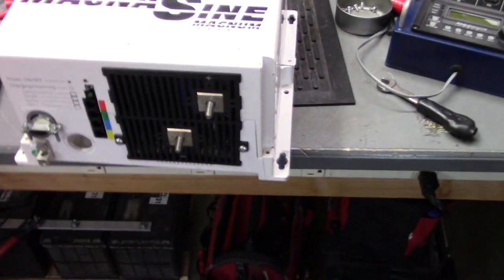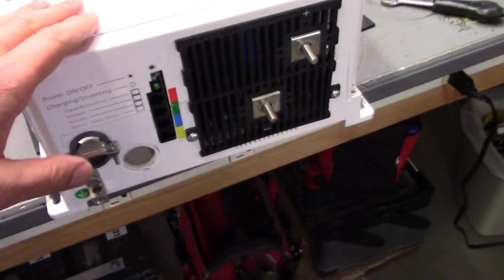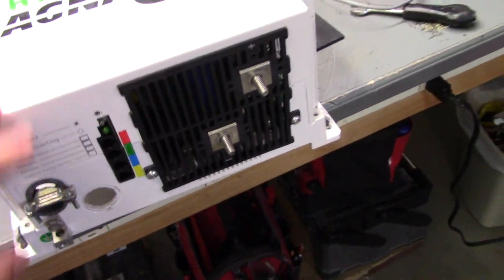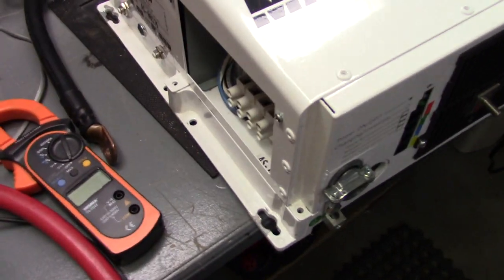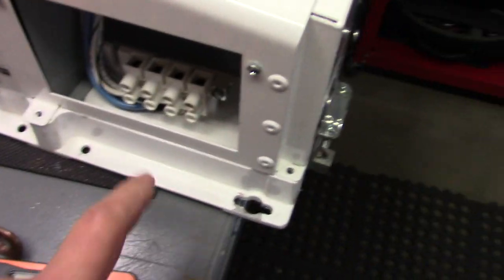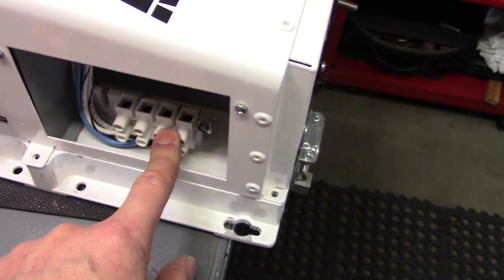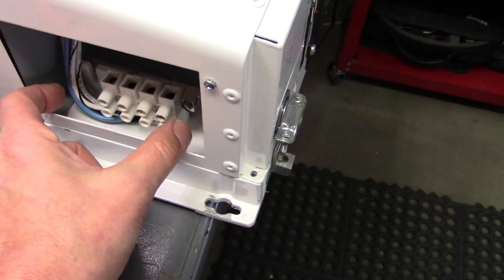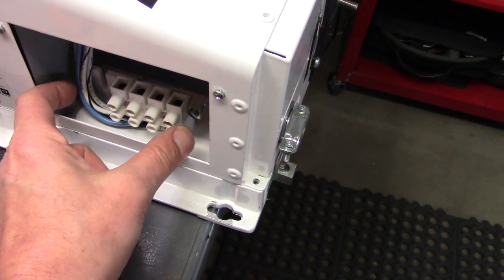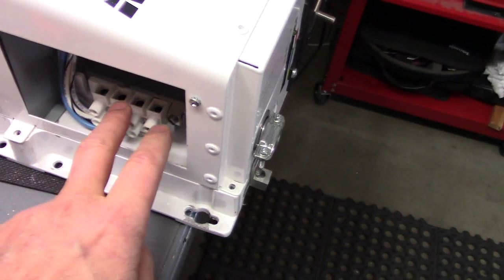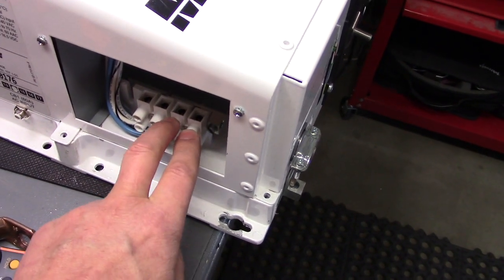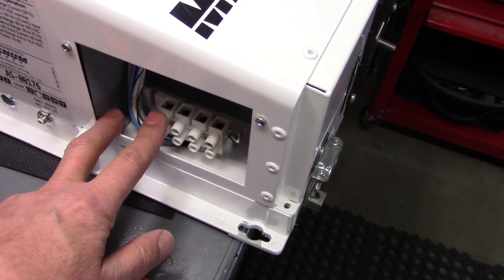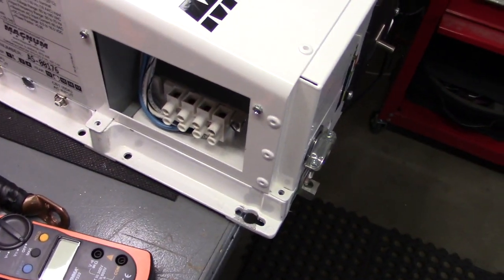It has the same inputs, outputs, all the same control lines and so on. One thing that is a little different, this one only has a single input, single output, single phase in, single phase out. The other Magnum inverters you usually have a six position strip here and you'll have a neutral with two line inputs and a neutral with two line outputs. So that's one major difference here.